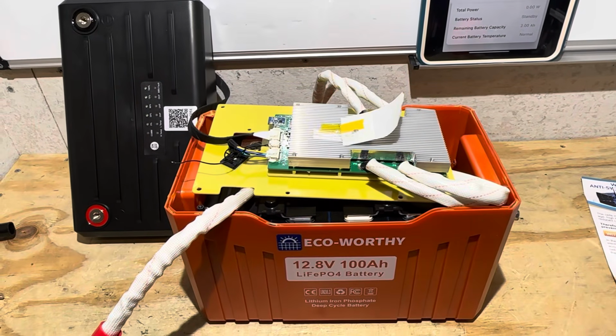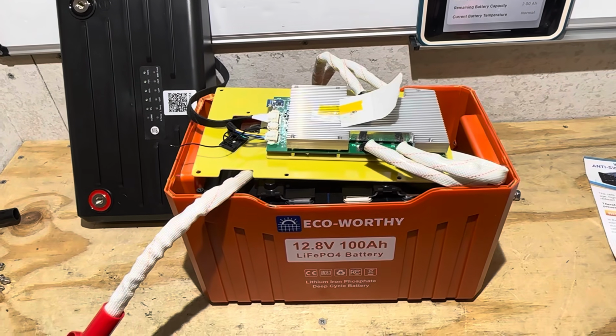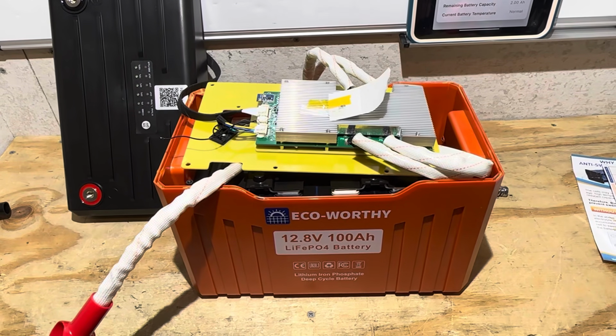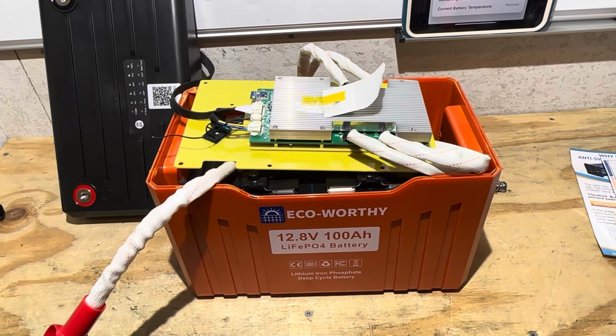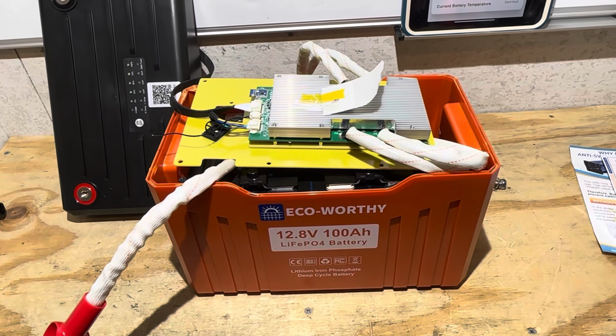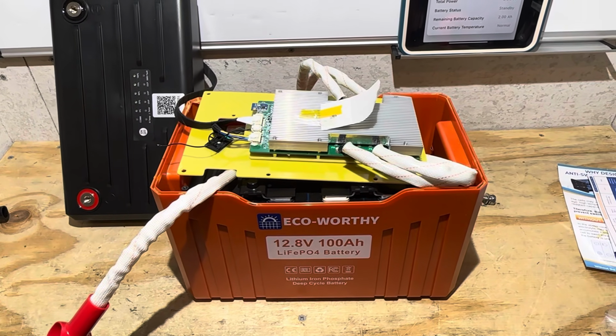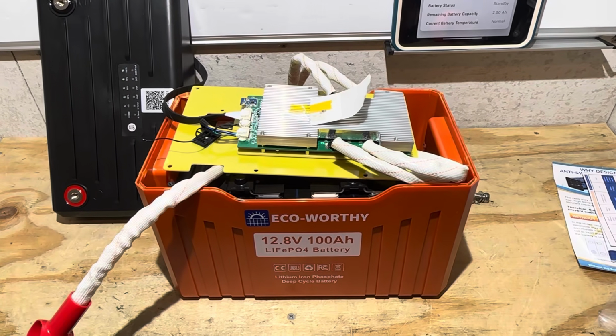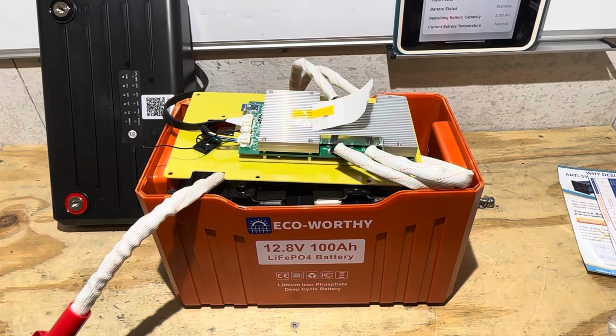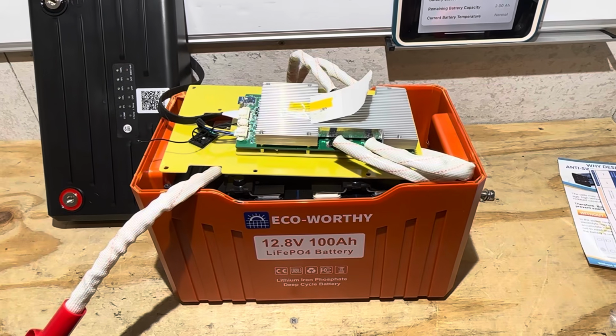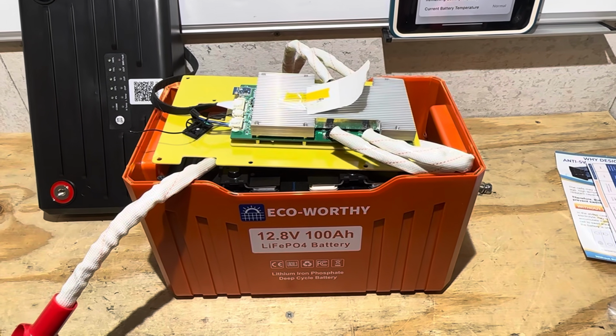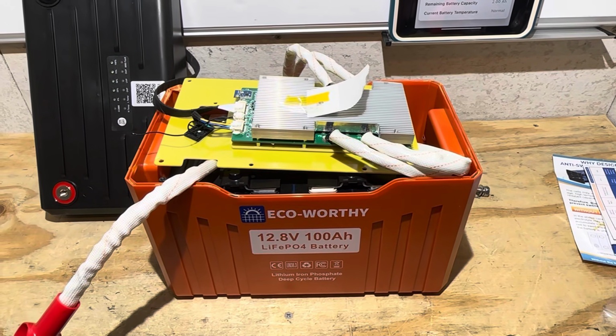Regarding capacity, here's how it's going to go. Someone's going to leave a comment or email me saying I need to cycle the battery 5, 10, 15, 20 times, etc., to realize the rated capacity. I'll tell you what, if it doesn't deliver rated capacity out of the box, that's a fail. You can get a battery a lot cheaper than this one and it'll punch out 104, 105 easy.